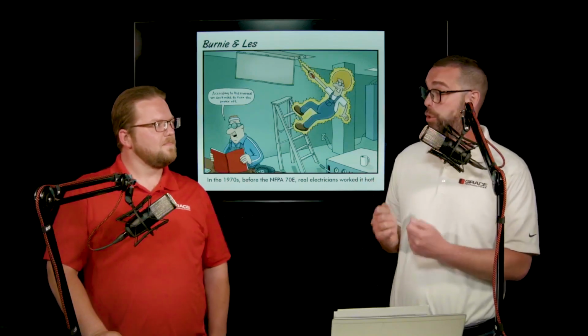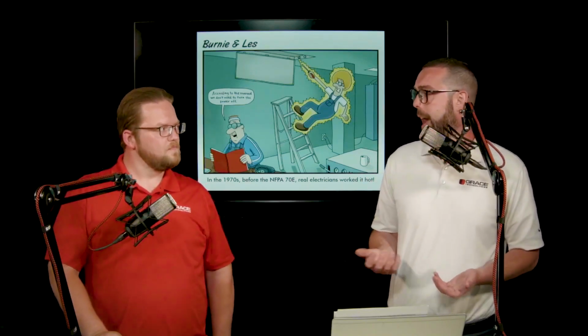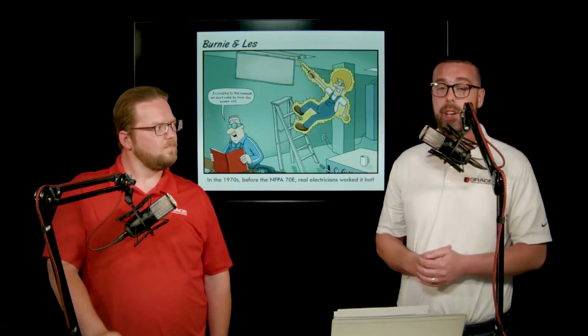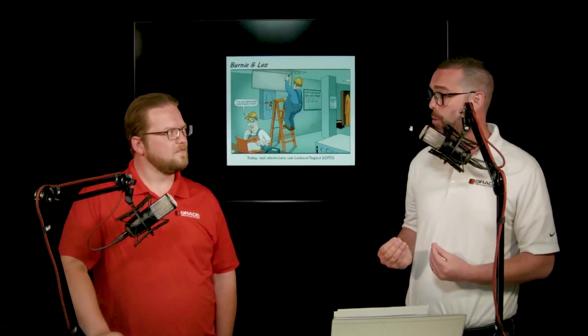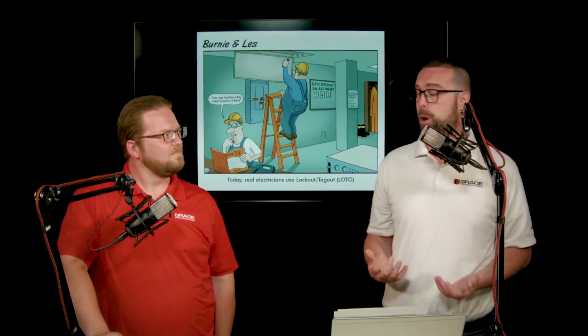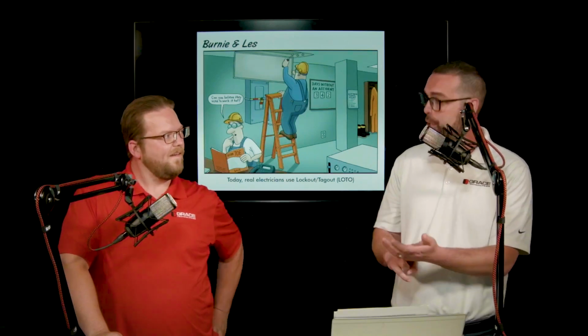So when you have your portable test instrument, we want you to test it to a known voltage source, just to ensure that the voltmeter is calibrated and working as it should. Absolutely. And then test that meter live at the check volt or the contact test point device that we offer, and test it live. Test it phase to phase to ground, and ensure that you're getting an accurate voltage reading. Flip your disconnect or isolator switch, test it dead at the device, phase to ground, and then again, test your meter back at that known voltage source to ensure, again, that your meter is calibrated and working as intended. So again, we're not necessarily changing that process. We're allowing the user to keep their equipment door closed and reducing that overall incident energy exposure. That's really what it's all about. Elimination, substitution, and engineering around that risk.